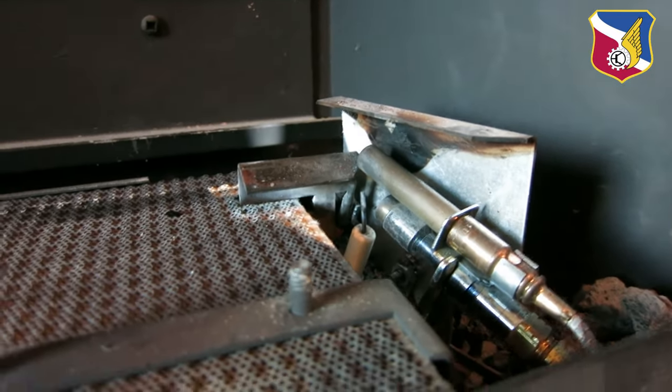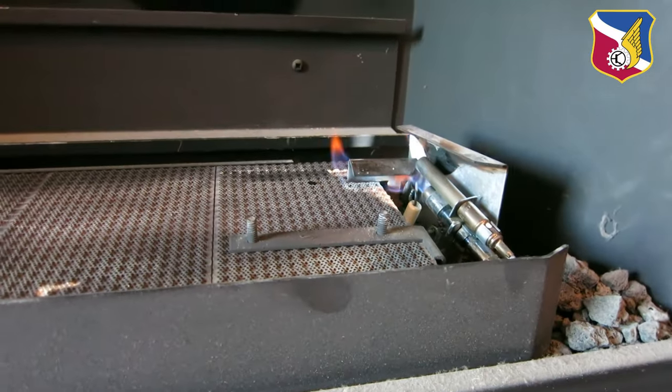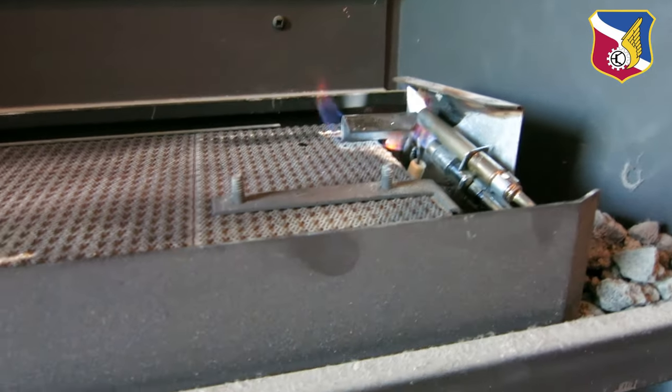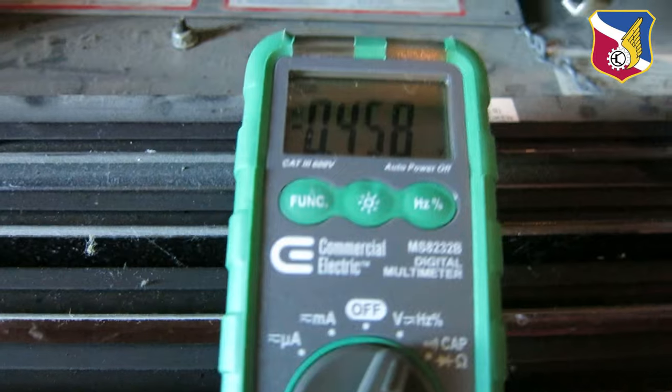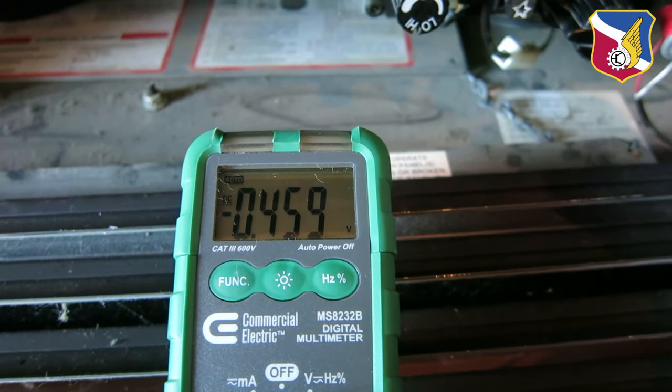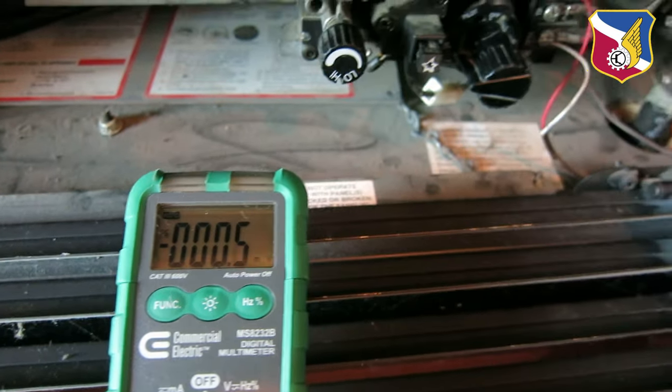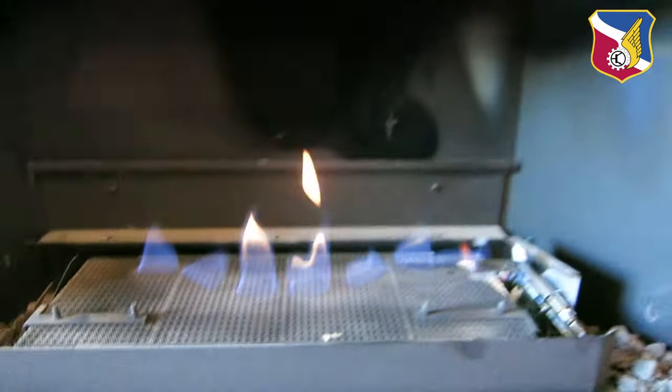So after it's clean, let's now turn it on, turn on the pilot and retest the millivolt level. So right now after cleaning it, it looks like the fire is burning a lot cleaner too. And as you can see I'm measuring the millivolt level. As you can see right now it went up to 458, which is a huge improvement than before.